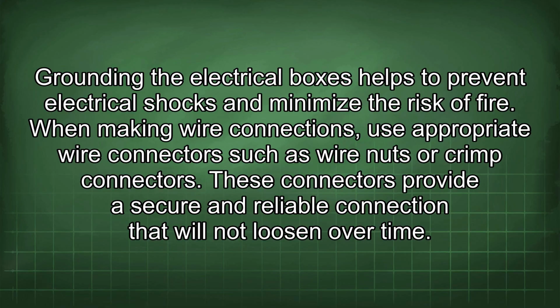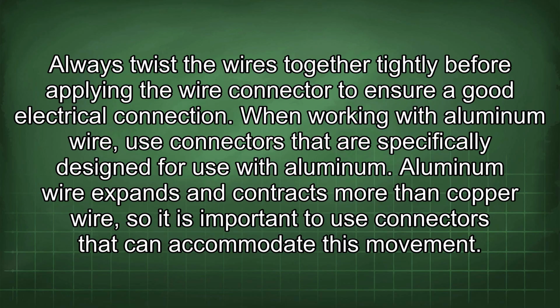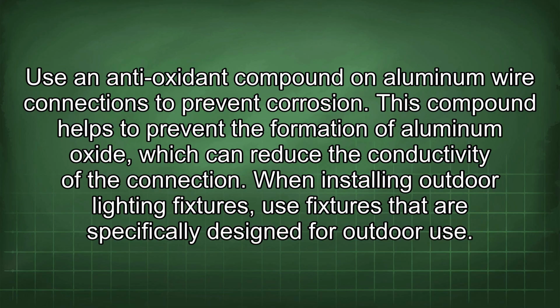When making wire connections, use appropriate wire connectors such as wire nuts or crimp connectors. These connectors provide a secure and reliable connection that will not loosen over time. Always twist the wires together tightly before applying the wire connector to ensure a good electrical connection. When working with aluminum wire, use connectors that are specifically designed for use with aluminum. Aluminum wire expands and contracts more than copper wire, so it is important to use connectors that can accommodate this movement. Use an antioxidant compound on aluminum wire connections to prevent corrosion. This compound helps to prevent the formation of aluminum oxide, which can reduce the conductivity of the connection.